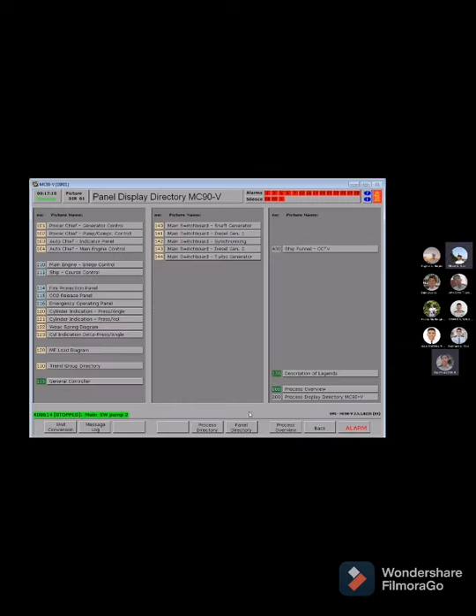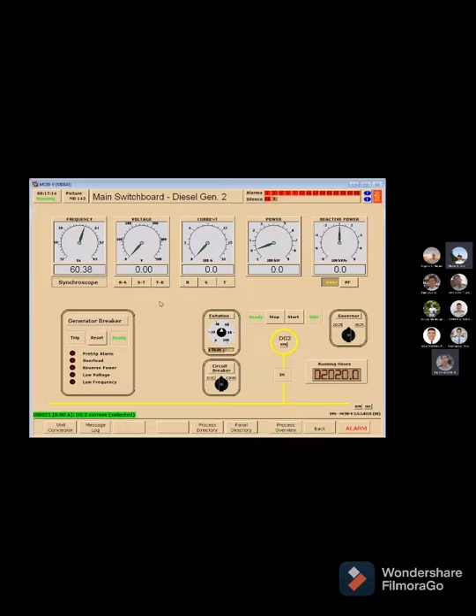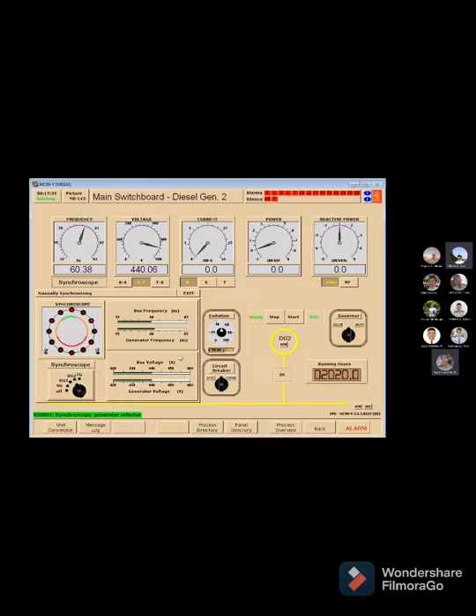Go to MD143, main switchboard diesel generator 2. Next. Check the frequency and the voltage by pressing either R-S, S-T, T-R, and current by pressing either R, S, T. Next. Press the synchroscope button, then select DG2, then adjust the frequency in a clockwise direction. Connect the breaker at 11 o'clock. Switch off the synchroscope. So we will connect the circuit breaker if the turning red light is at 11 o'clock, which is here. So let's wait. Okay, it's now connected.